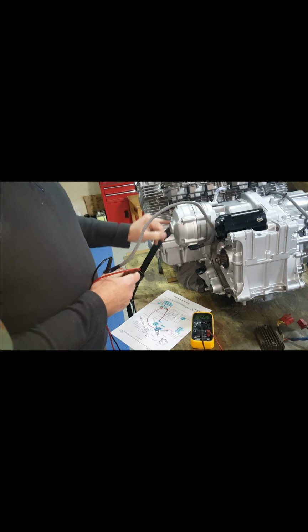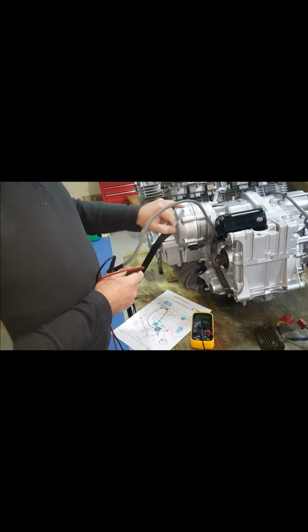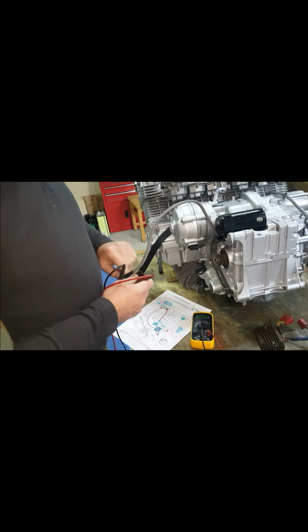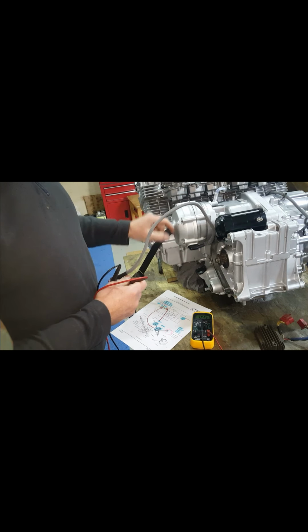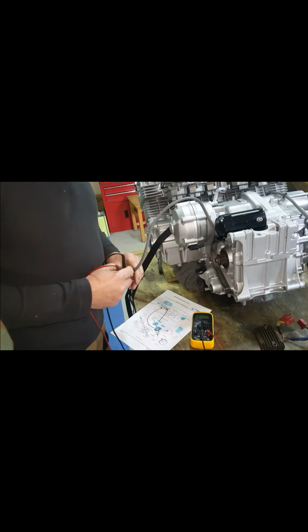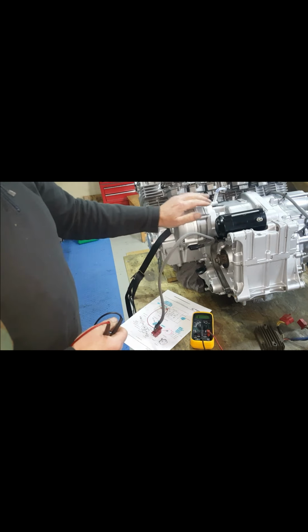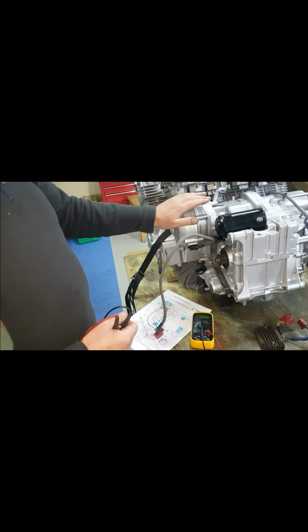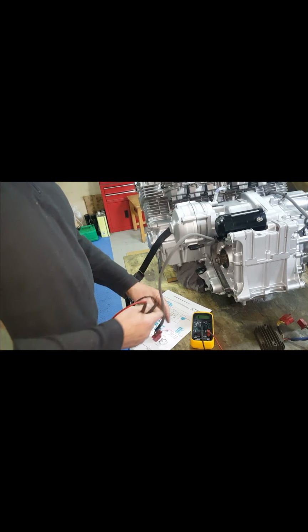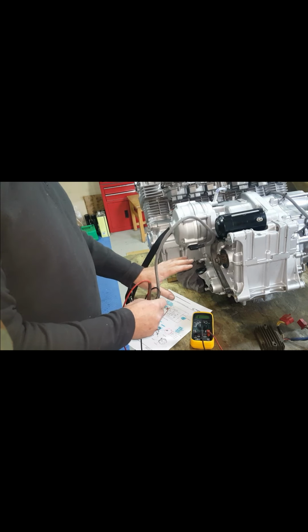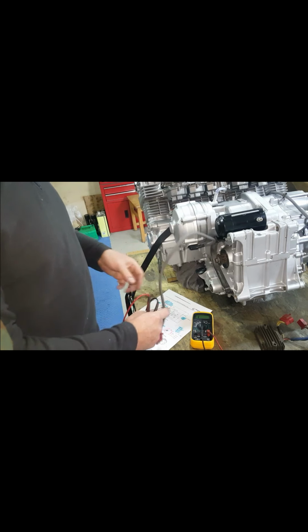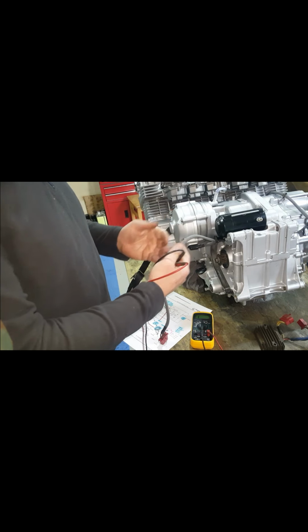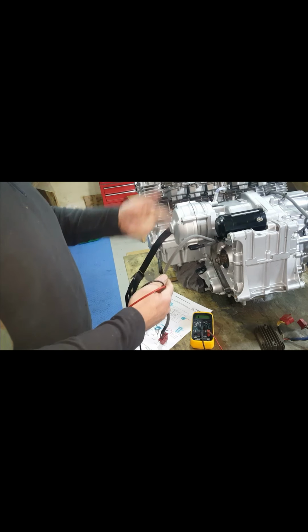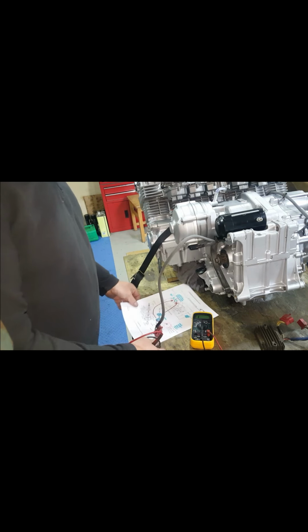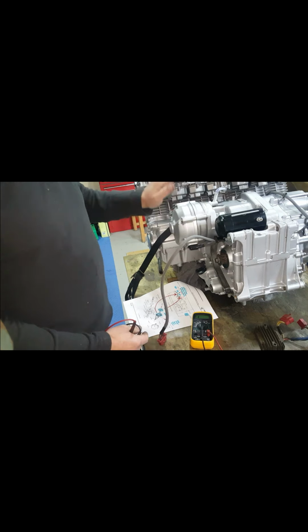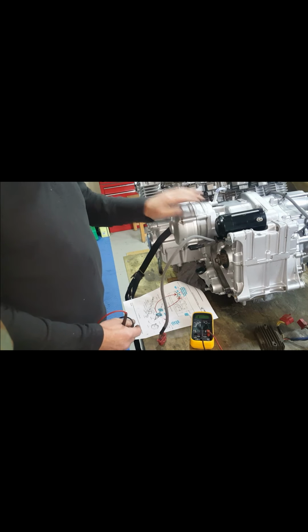So when you measure directly across the slip rings of the rotor, then you would expect that to measure about 3.5. There's about 1 ohm lost through this cable and through the brushes into the slip ring. So that's good. One thing I would say is, when you test this, just make sure that you crank the motor over first, because when I came to do this test, I luckily pre-tested it. This is reading about 30 ohms, and basically what's happened is some oxidization has got between the copper and the brushes. As soon as I turned it around a quarter of a turn, it was fine. So now we've tested the stator and the rotor as being fine.